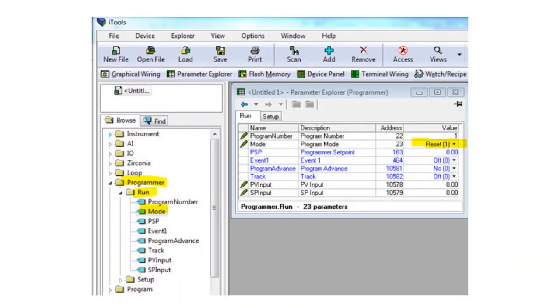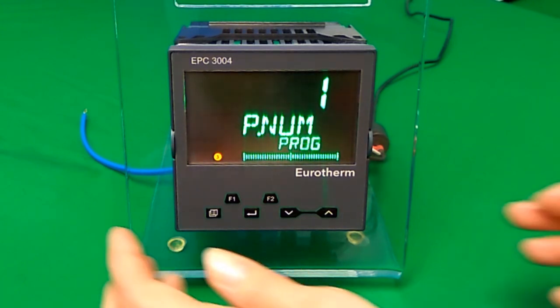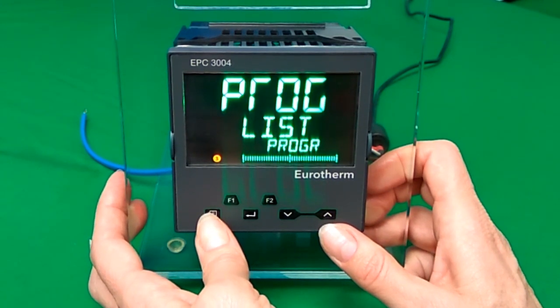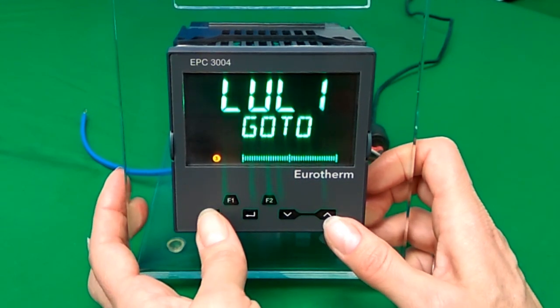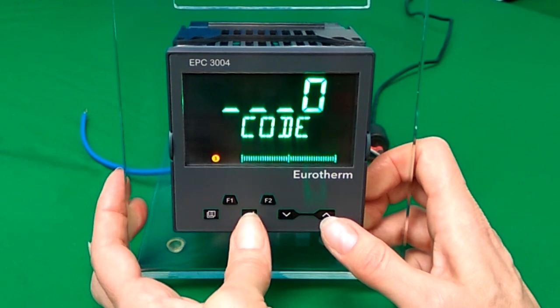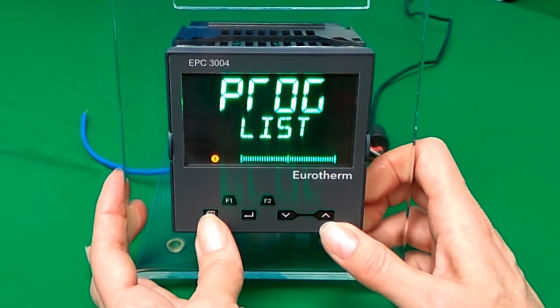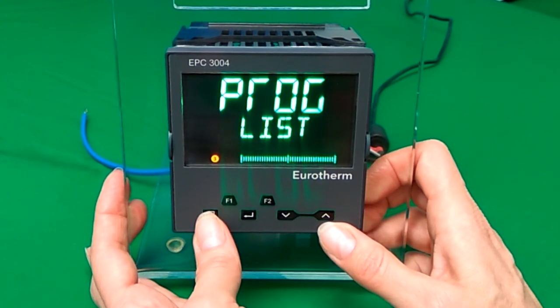The screenshot shows you iTools to help you recognise the parameter menu that you're in. Level 1 access allows only read access to these parameters. If you enter level 2 and then press the page button, you'll have read/write access to these parameters and you'll be able to see the other parameters as well for the setpoint programmer editor features.